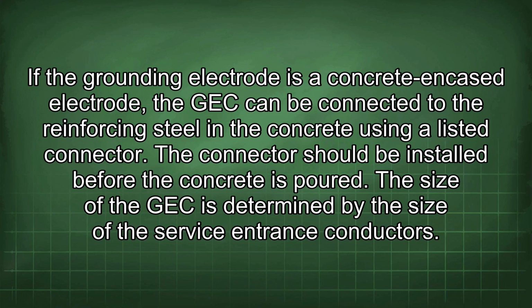If the grounding electrode is a concrete encased electrode, the GEC can be connected to the reinforcing steel in the concrete using a listed connector. The connector should be installed before the concrete is poured.